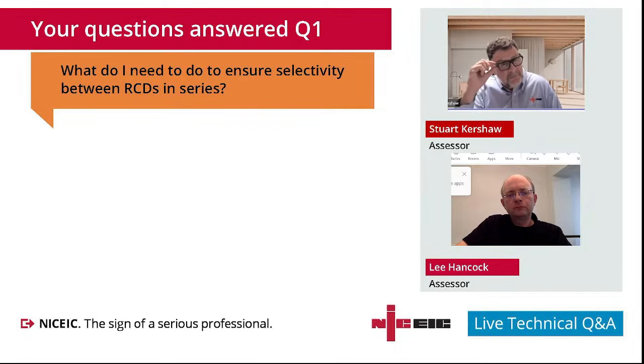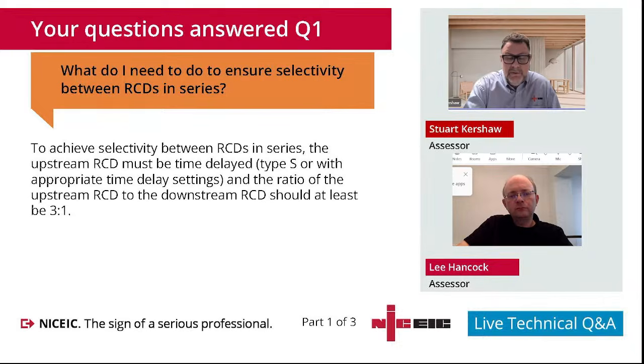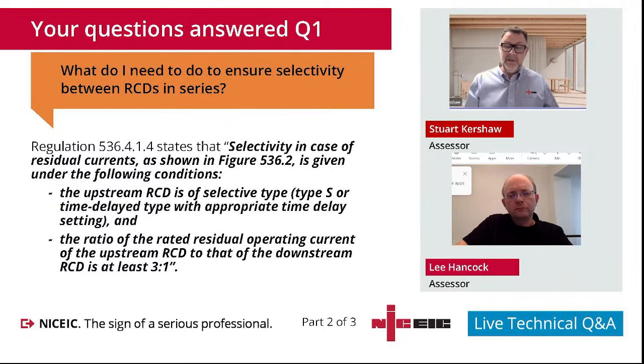Yeah, obviously RCDs in series, we need to ensure requirements. So we're looking at upstream RCDs, and obviously two 30 milliamp RCDs in series will not give you selectivity. So therefore we're going to have to look at regulation 536.4.1.4, which states, as shown in figure 536.2, some RCDs in series, and we're looking for a ratio of 3:1.